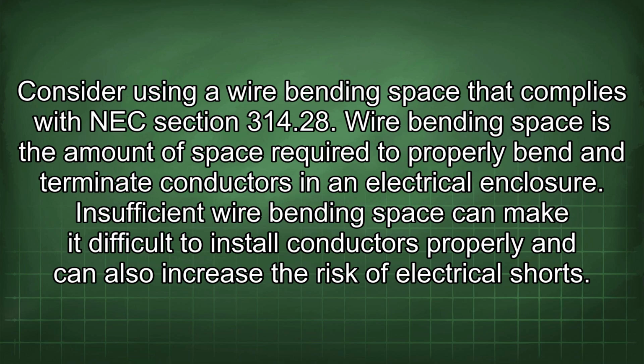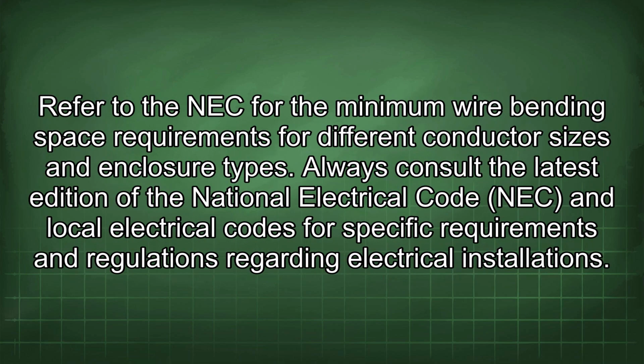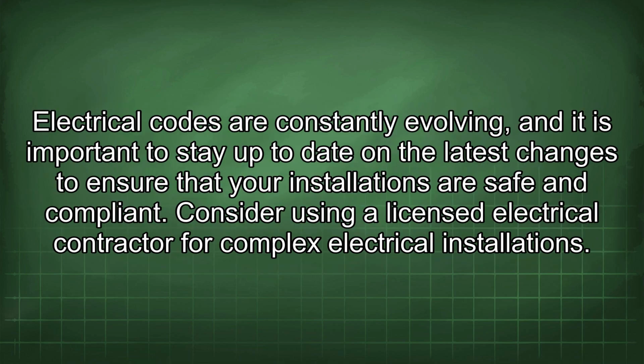Consider using a wire bending space that complies with NEC Section 314.28. Wire bending space is the amount of space required to properly bend and terminate conductors in an electrical enclosure. Insufficient wire bending space can make it difficult to install conductors properly and can also increase the risk of electrical shorts. Refer to the NEC for the minimum wire bending space requirements for different conductor sizes and enclosure types. Always consult the latest edition of the National Electrical Code (NEC) and local electrical codes for specific requirements and regulations regarding electrical installations. Electrical codes are constantly evolving, and it is important to stay up to date on the latest changes to ensure that your installations are safe and compliant.